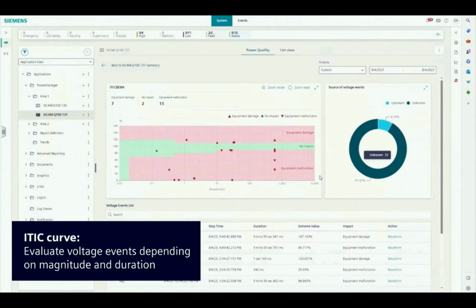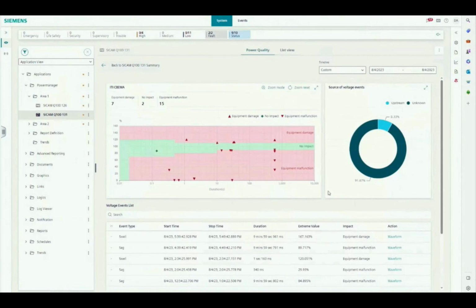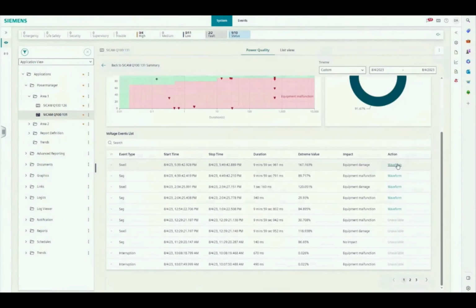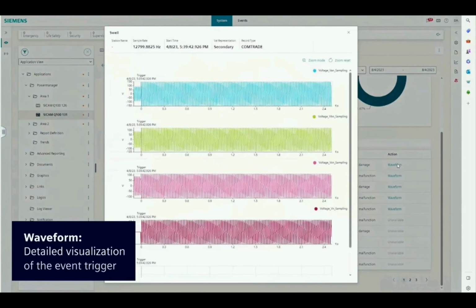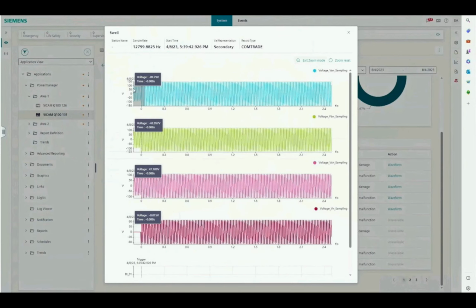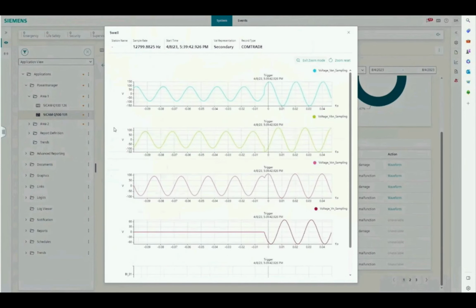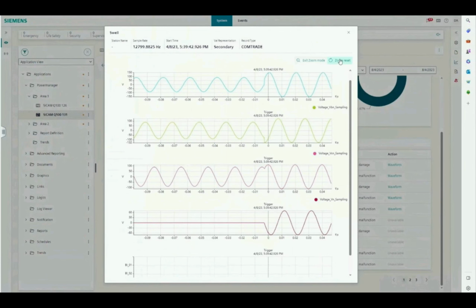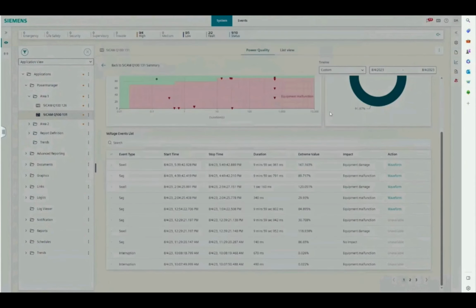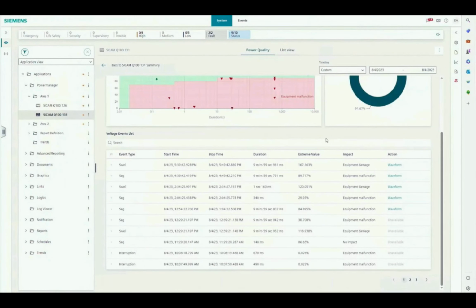You can see if you have sags and swells according to the ITIC curve or CBEMA curve, also SEMI-F47 visualization. It's possible to see if the sag or swell has an influence on your IT equipment or production, and drill down into the actual waveform to see the trigger event and the reason for it, so you can derive measures from this.